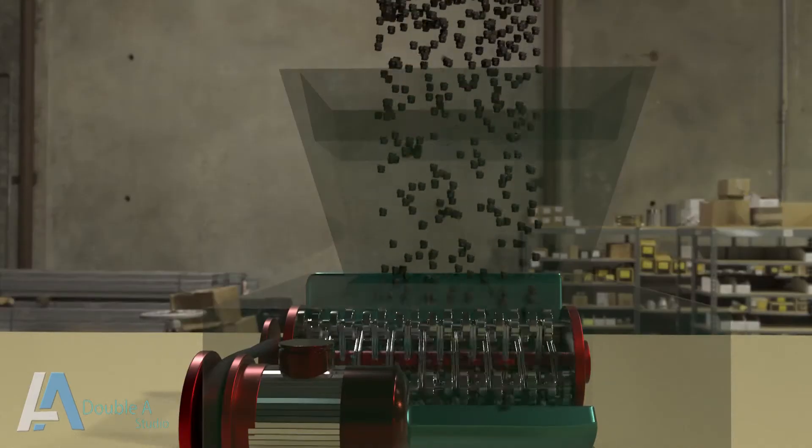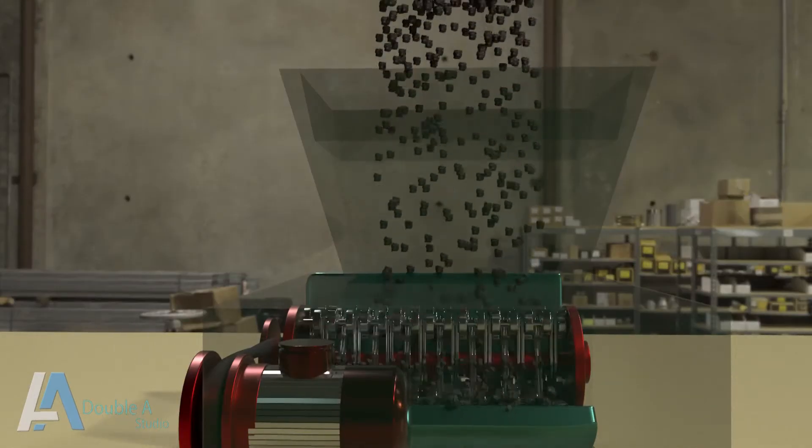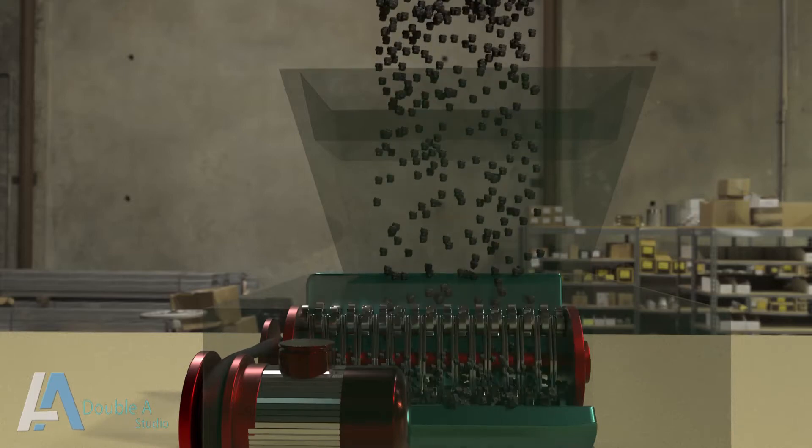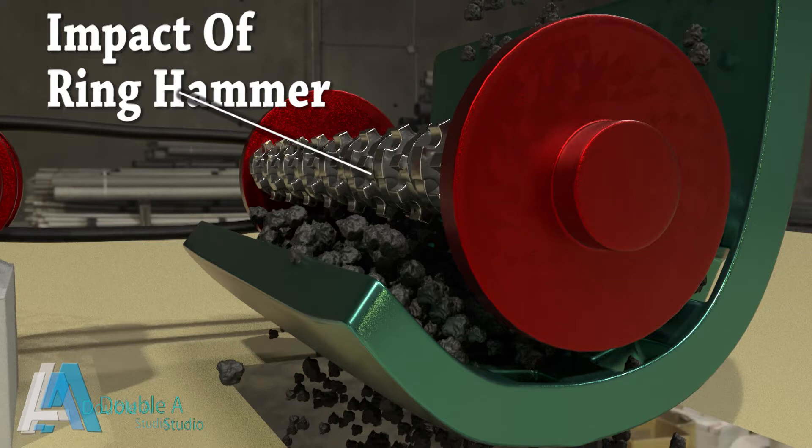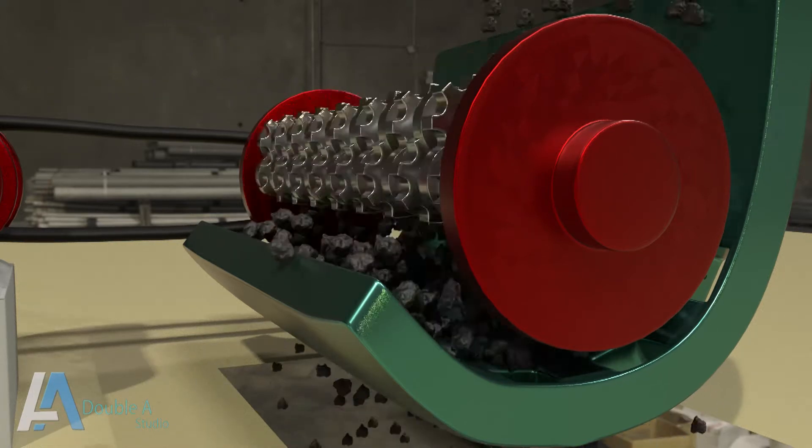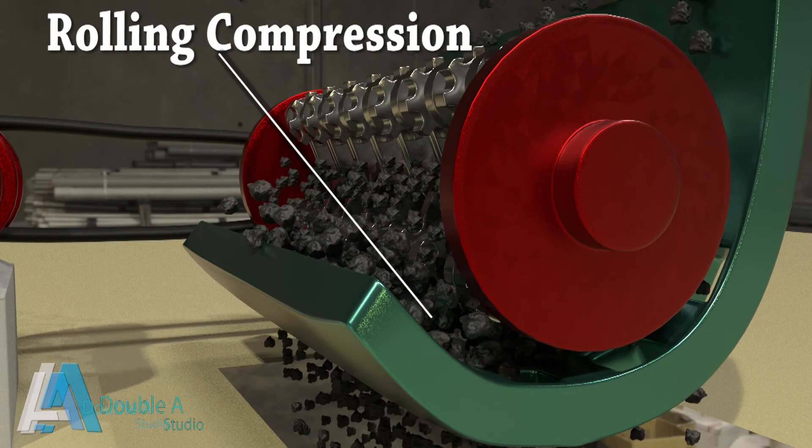When coarse coal is fed from the chute, crushing takes place by two types of action. One is by the impact of ring hammers and the other is by rolling compression between crushing plate and ring hammer.